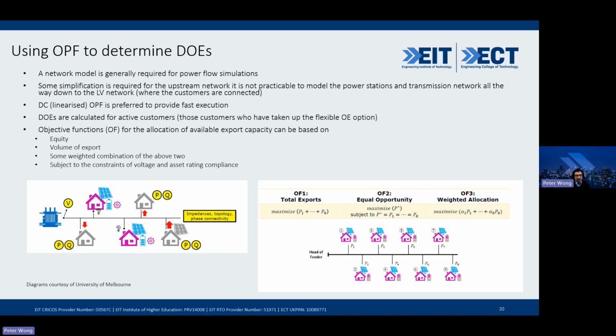The DOEs are only calculated for customers we call active customers, those that take up the flexible OE option, because some customers don't do that. There's also existing customers who already have solar PV, and we can't retrospectively go back to them and say they need to accept a limit now. So it's only for the new customers coming on. You model those flexible customers, and calculate the DOE for them.